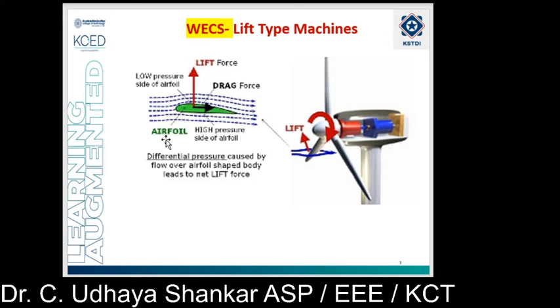Drag devices are less efficient and turn slower than wind speed. They produce high torque and thus are suitable for pumping applications. At high wind speeds they will spill the wind instead of producing more energy, and thus they do not benefit from the high energy density available in the wind. In case of lift blade design, it employs the same principle used in aeroplanes, kites, and birds to fly.